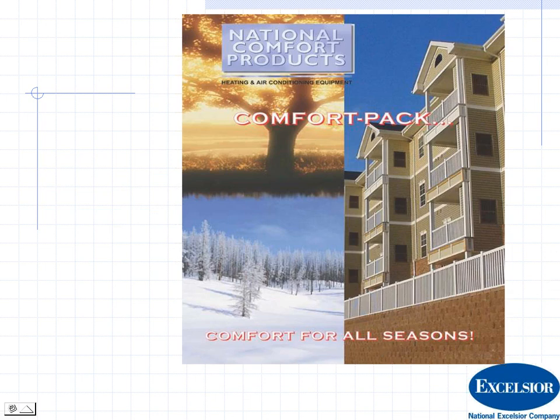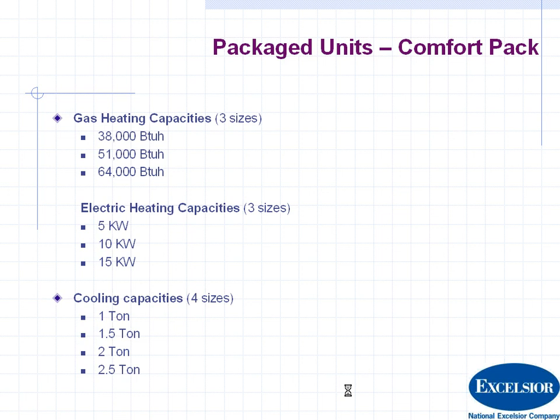Let's talk a little bit about the comfort packs. The comfort packs are the packaged units. This is what you see mostly in replacements. The package units go in 3 sizes, 38,000, 51,000, and 64,000 BTU heating capacity, and these are 80%. These are the CPG units, for comfort pack gas. They have electric models, CPE units, which are comfort pack electric, in 5 kW, 10 kW, and 15 kW heats. Again, you don't need much more than that for multifamily work.